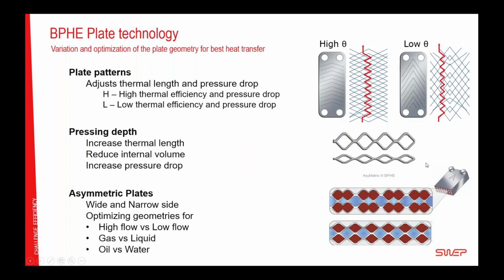Another parameter that SWEP have in our different models is the pressing depth of the plate. A big pressing depth gives a low pressure drop and a short thermal length. And a little pressing depth has higher pressure drop and longer thermal length. You have to keep your tongue in your mouth in the right way to say it, but it becomes kind of logical when you see it. This is more squishy, so it will be smaller, higher pressure drop, but the fluids will also be closer together, so it will be more energy efficient, so to say.